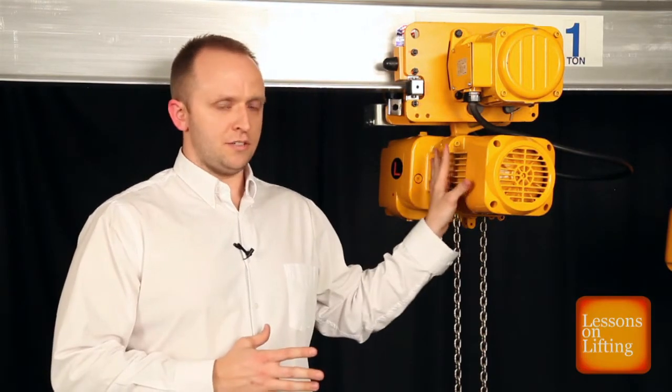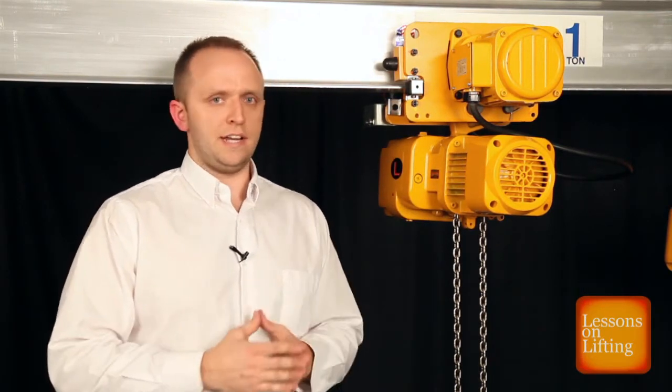Do not change the wiring of the trolley hoist at that point. And once you've done that, if you encountered that problem, once you've switched any two legs, check it again and it should run properly. And then you know you have completely, successfully completed a voltage change on your unit.